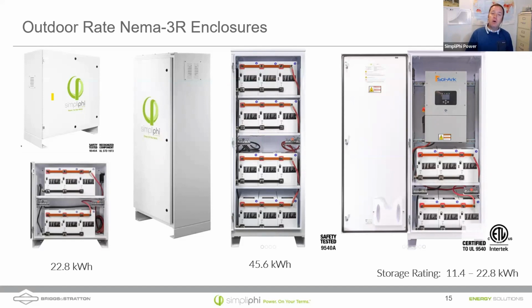I've also seen people put insulation under the batteries, because if you think about this battery cabinet, it's a giant metal cabinet, right? So there's a few ways to lose heat, right? Through conduction, convection, and radiation. So if we can prevent this metal cabinet from radiating out the heat or through conduction, we can keep the batteries a little bit warmer and use what little internal resistance there is in a battery that's generating its internal heat to contain that heat and keep it where we want, which is near the cells, to keep them a little bit warmer.